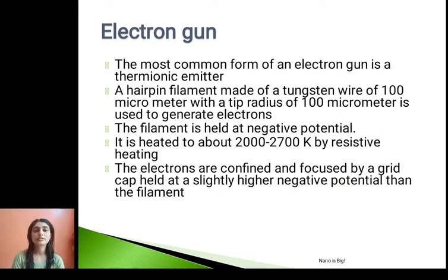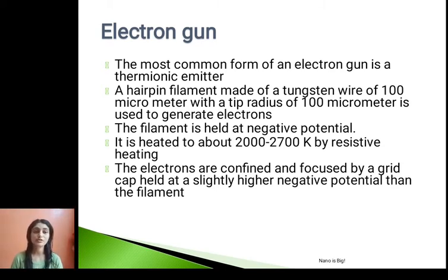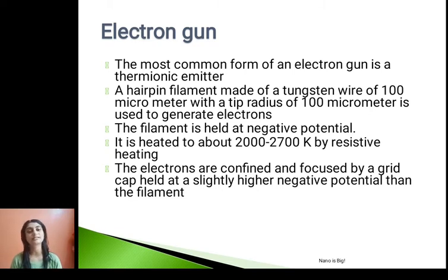The most common form of an electron gun is a thermionic emitter. In a thermionic emitter, when you supply heat energy, at the output you get electrons. A hairpin filament made up of a tungsten wire of around 100 micrometers with a tip radius of around 100 micrometers is used to generate electrons. The filament is held at negative potential and is heated to about 2,000 to 2,700 Kelvin by resistive heating. The electrons are confined and focused by a grid cap held at a slightly higher negative potential than the filament.